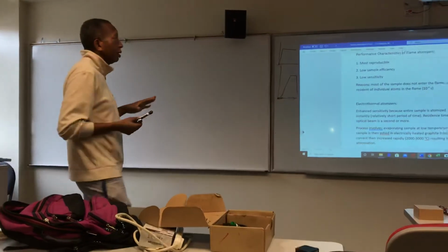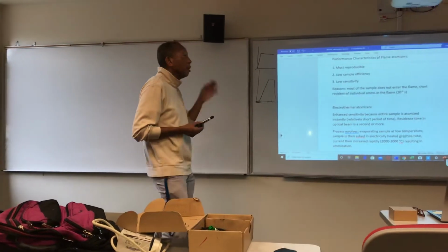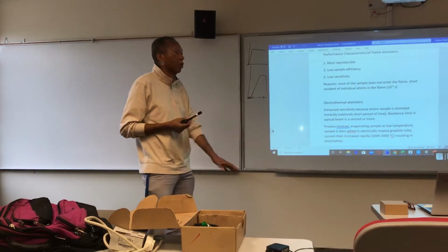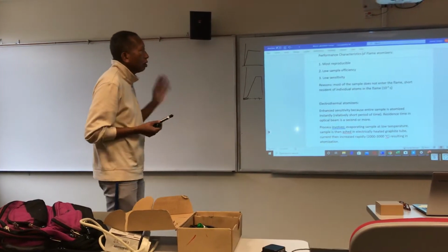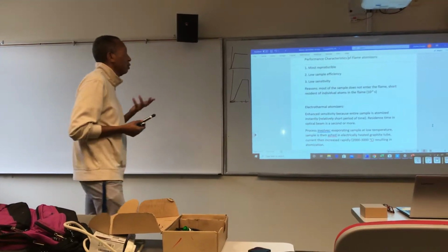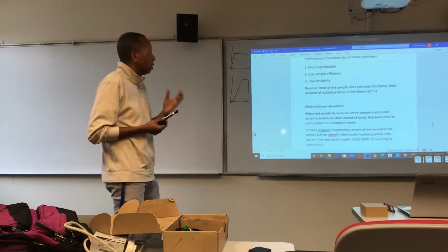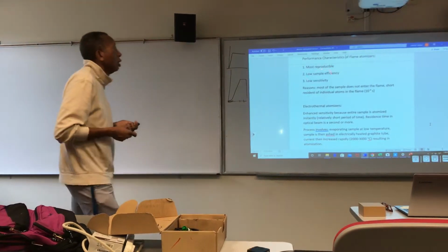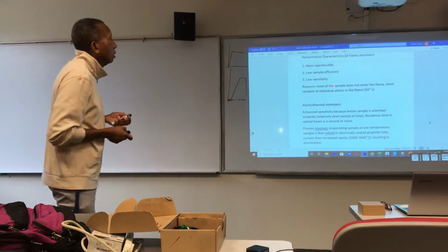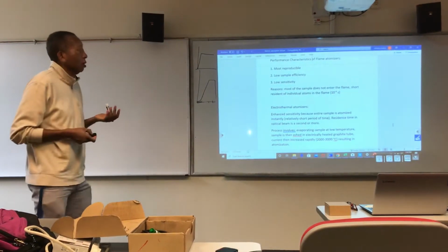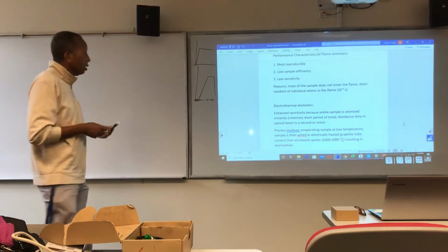So in effect, in flame atomizers, over 90% of your sample is in that bottle that you see below the instrument. Just a really, really small percentage. I would guess less than 1% of what the sample actually goes into the flame. So the sample efficiency is low, and the sensitivity is low. And the reason is that most of the sample does not end up in the flame. That's one.